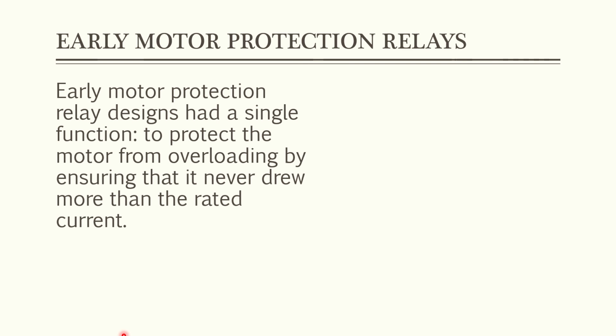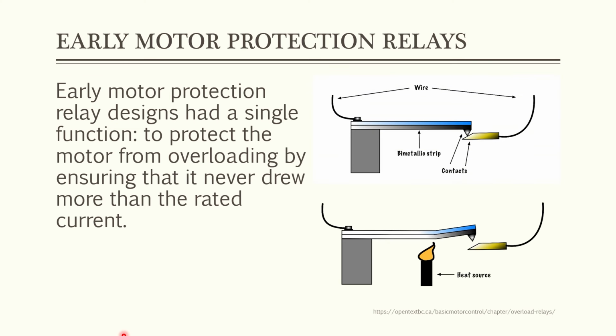Early motor protection relay designs had a single function, and that is only to protect the motor from overloading by ensuring that it never drew more than the rated current. So the function of early motor protection relays was a single function only, which is to protect the motor from overloading and make sure that it never drew more than the rated current.